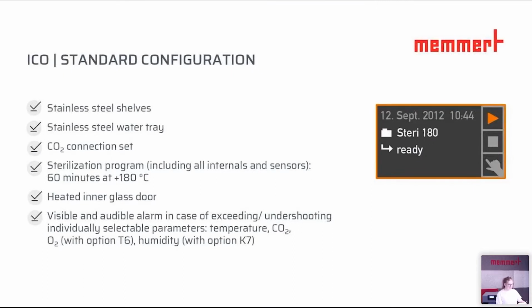Okay, moving on to our standard configuration. What actually do I get when I order an ICO? Well, you're going to be provided with stainless steel shelves. And I say shelves, not the usual Memmert grids. This is being done for a good reason, as it simply provides more resistance against vibration, since customers usually put Petri dishes on top of them.